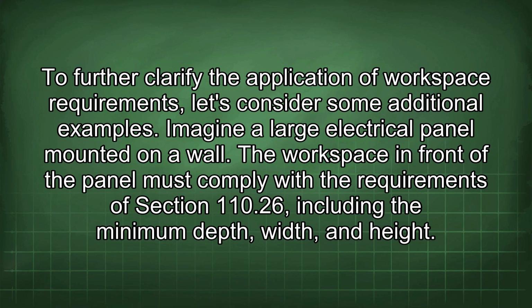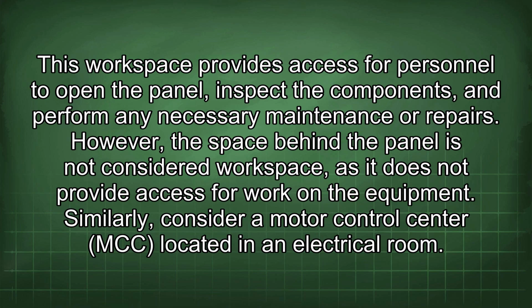Imagine a large electrical panel mounted on a wall. The workspace in front of the panel must comply with the requirements of Section 110.26, including the minimum depth, width, and height. This workspace provides access for personnel to open the panel, inspect the components, and perform any necessary maintenance or repairs. However, the space behind the panel is not considered workspace, as it does not provide access for work on the equipment.